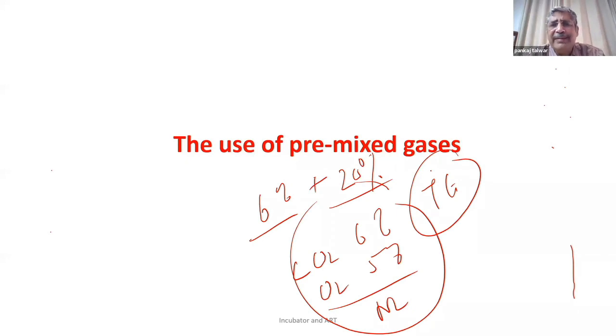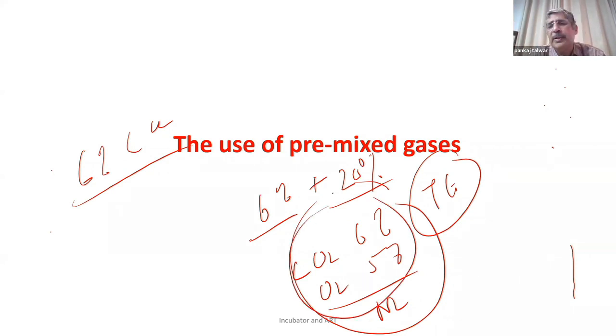But the only issue with the tri-gases is that they're not available in tier 2 cities. So tri-gas, this is the problem. It is difficult to measure. We can record 6% CO2, we can check by a device, an analyzer. But there are no devices to check, or no ports available to check this gas mixture in the incubators. They are not all that advanced.